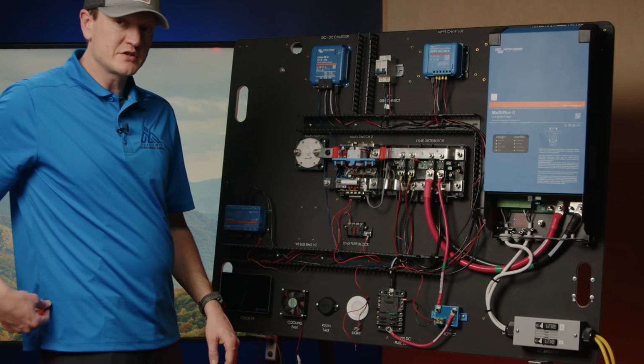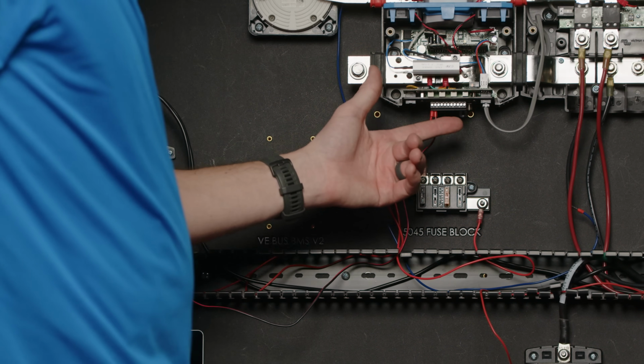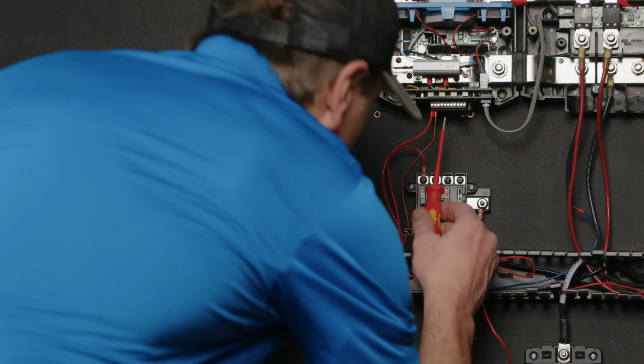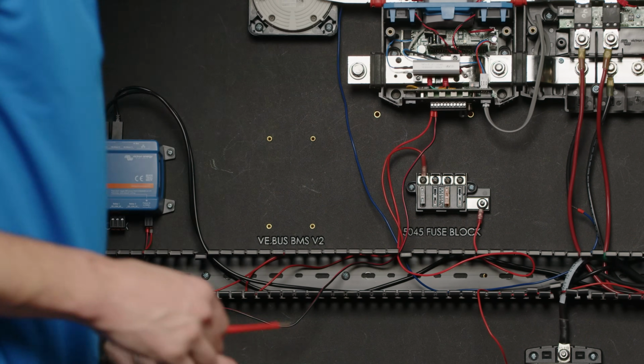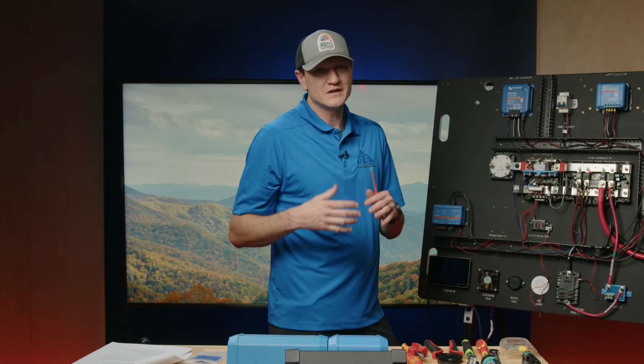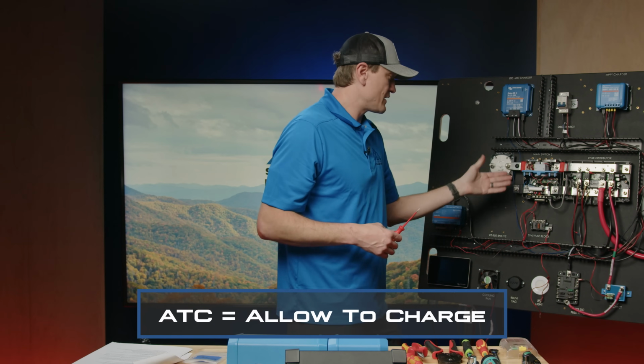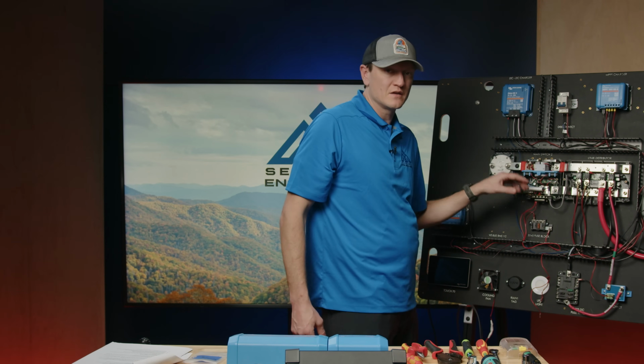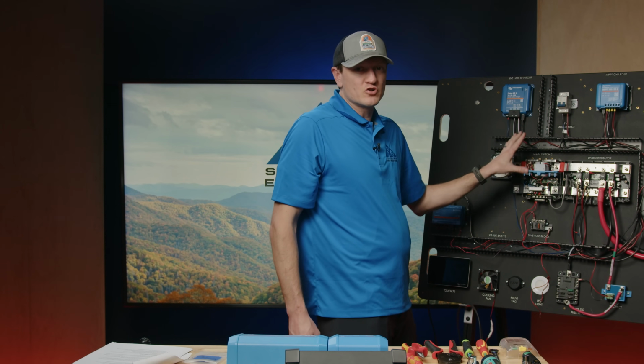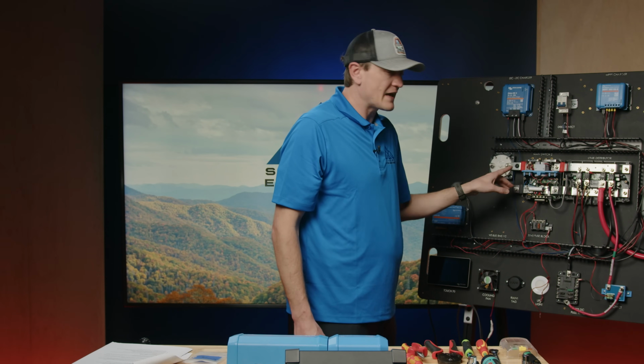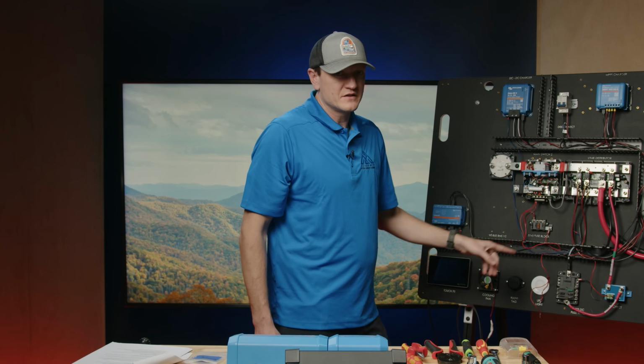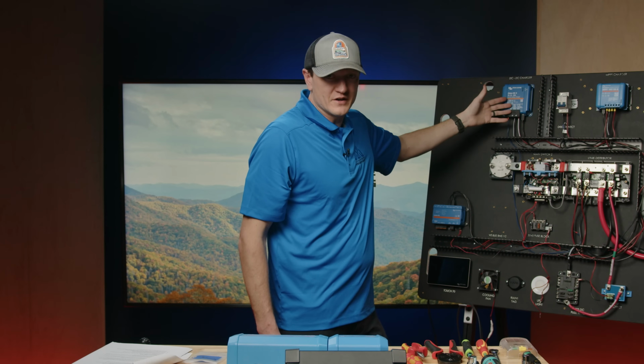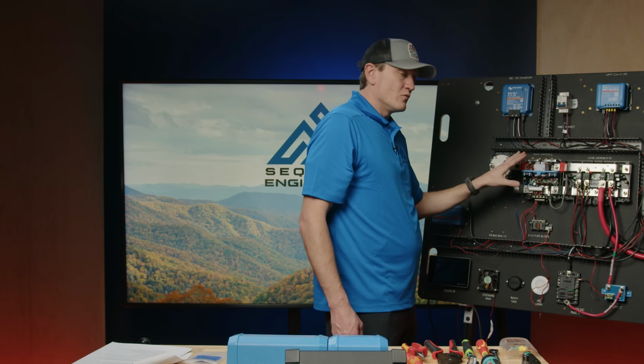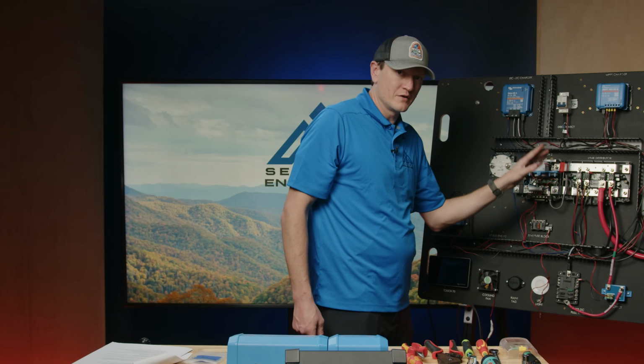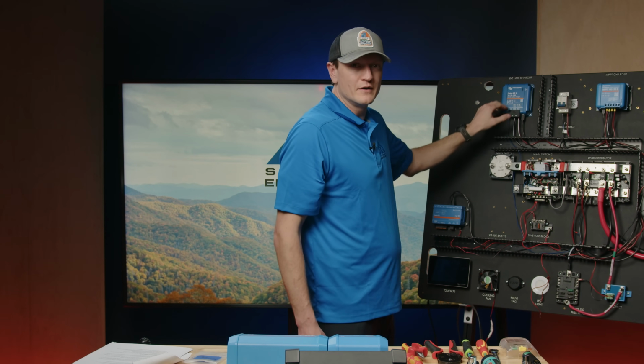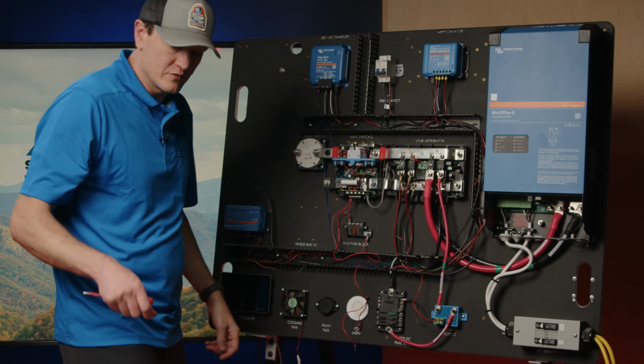Next we want to provide power to pin 3 and pin 4. Pin 3 and pin 4 are part of the Allow to Charge system. We send power up to pin 3, and when the BMS wants to allow chargers in the system to charge, it sends that voltage over to pin 4, which sends a signal up to the remote port on a charging device, telling it to work. Let's make that connection using one of these short pre-made wires.